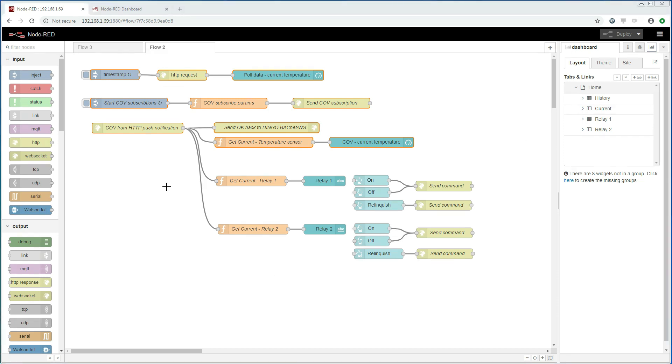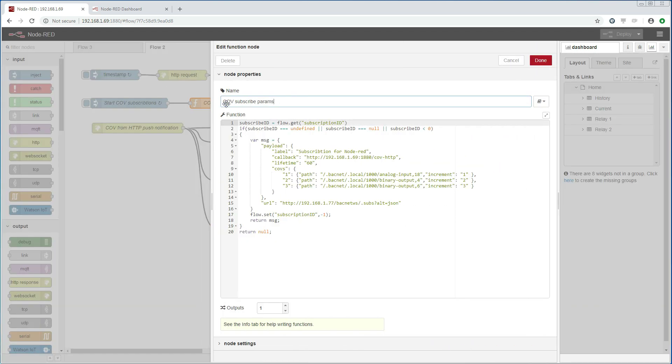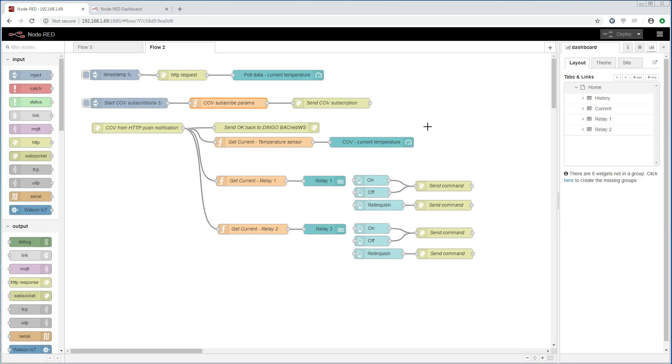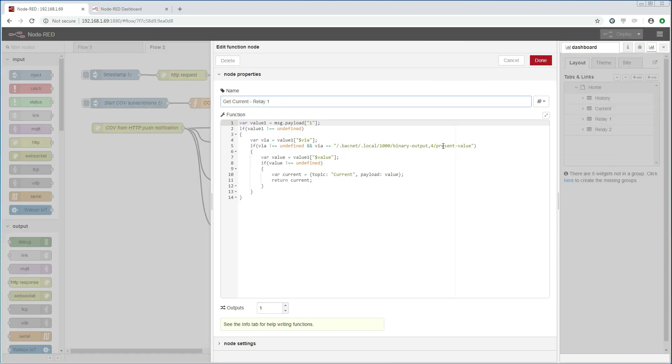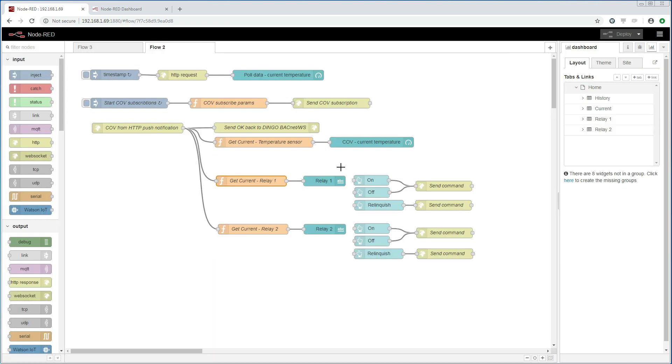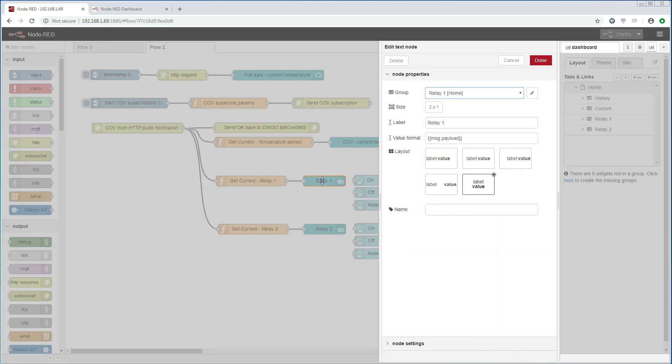So regarding the relays, the first thing we want to do is to get the state of the relays as they happen. So I go into the COV subscription parameters that we created in the last demonstration, and I have added the BACnet objects that are associated with the relays. I also added two functions that are connected to our HTTP endpoint. And these functions will go through the change of values that we are receiving from the other Dingo device. And we pick the value for each of the relays. These values will be either 1 for on or 0 for off. I have then added two text nodes that will get these values and present them in the dashboard.